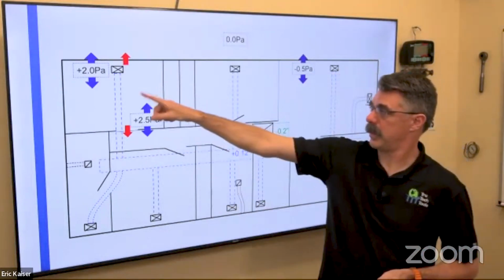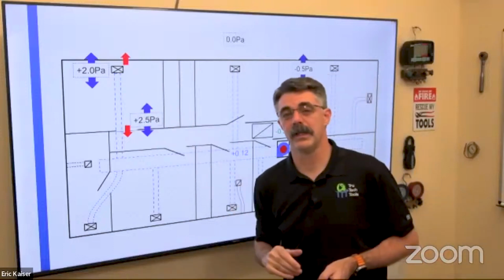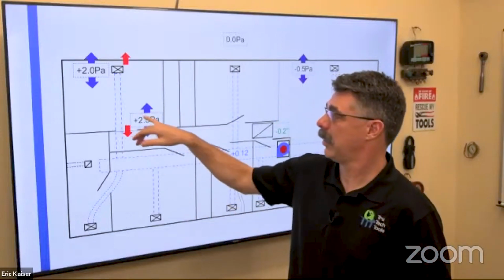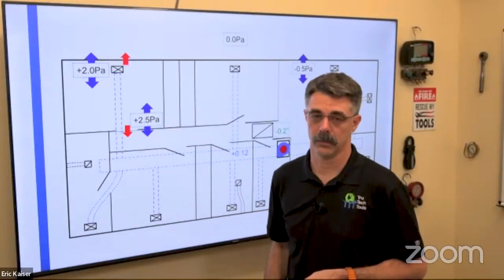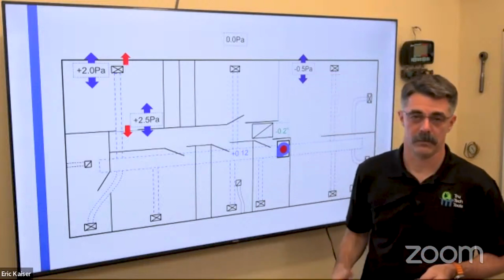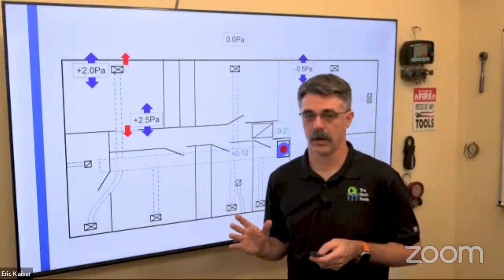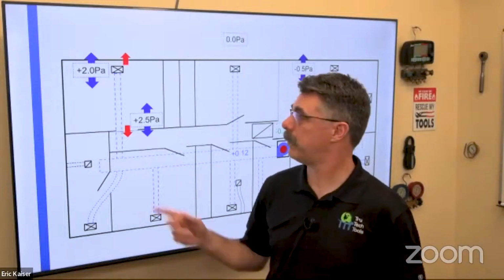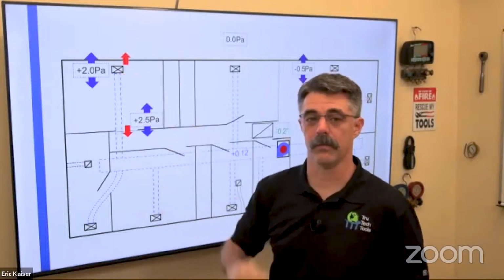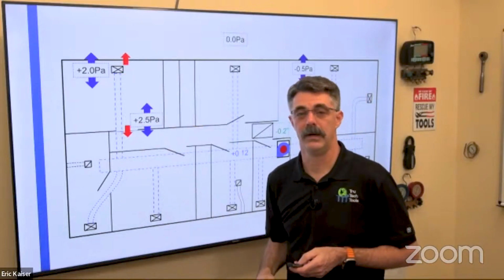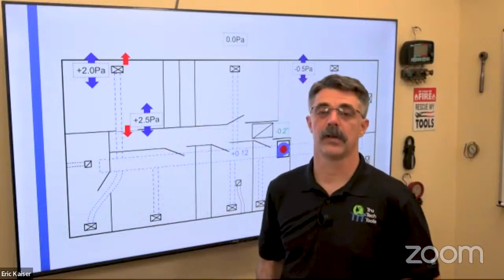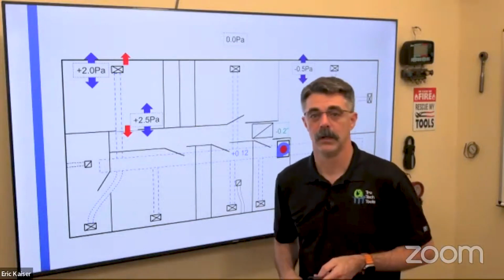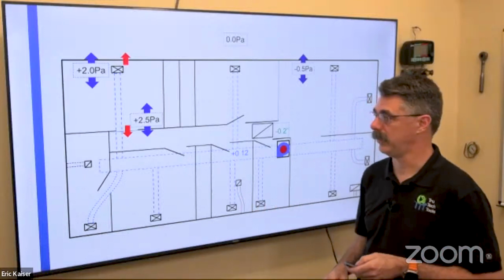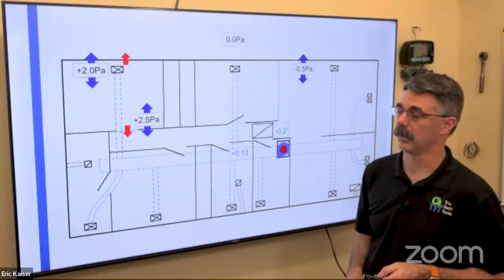So now we have a pressure differential. Typically, we want to see less than 3 pascals of pressure in a room. That's not a hard and fast rule, because it really depends on how big the leaks are. If you have a very leaky room to the outside, it doesn't necessarily create a big pressure. So it all depends on how leaky that house is and where the leaks are.